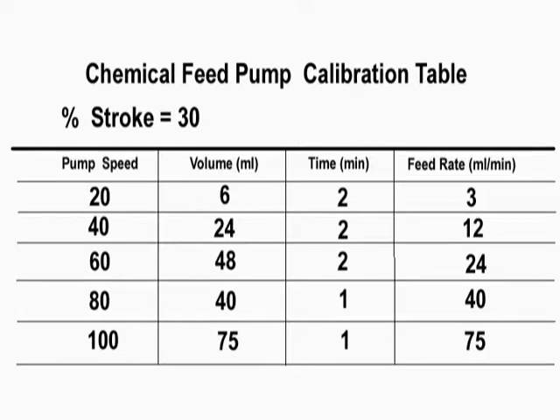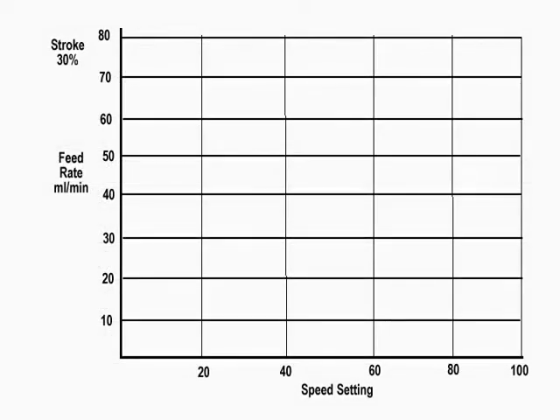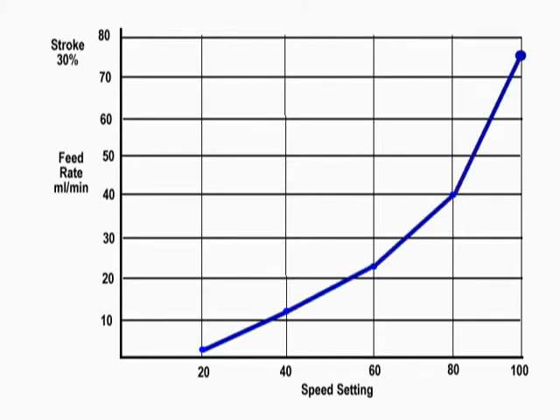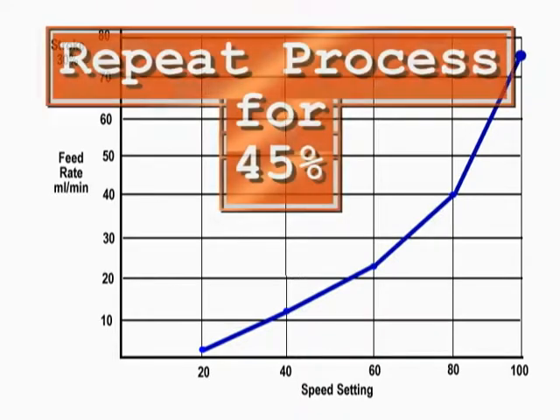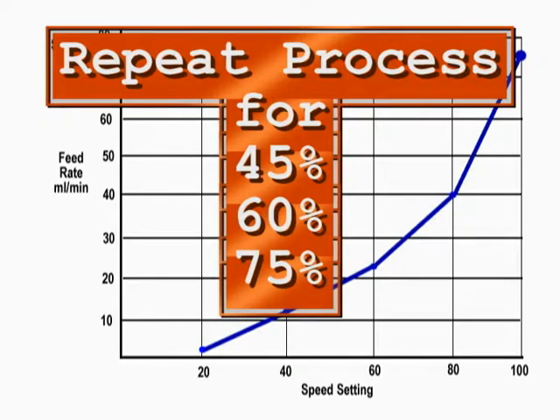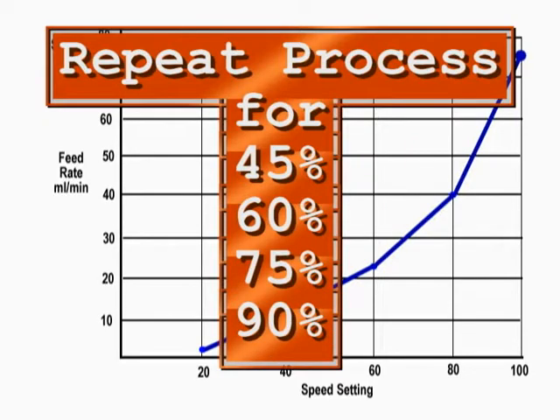The results should be graphed, as shown in the example. By drawing a line through the points, the operator can illustrate the delivery characteristics of the pump. The process should be repeated for stroke settings of 45, 60, 75, and 90 percent. The operator can then compare the various results and choose the most linear curve for normal pump operation.